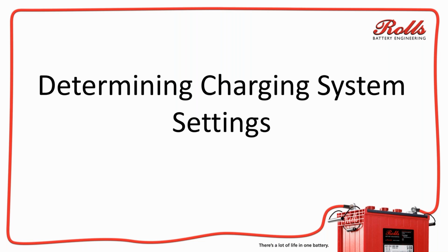All right. So can oldish flooded lead acid batteries show high specific gravity, thus 1265, 1275, but still be so sulfated that it is next to done? Yes. Now, as batteries age, generally the most common thing that happens to them, especially when they're being grossly undercharged, is you start to see the specific gravities fall. Okay? So the specific gravities will fall over a period of time.